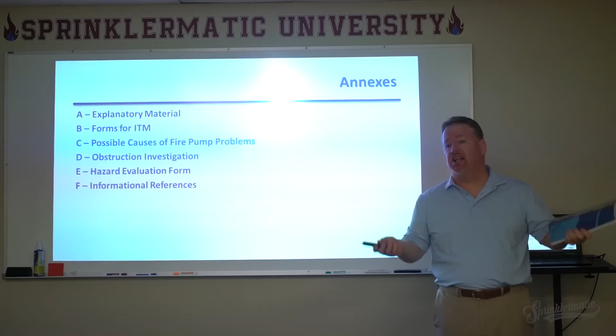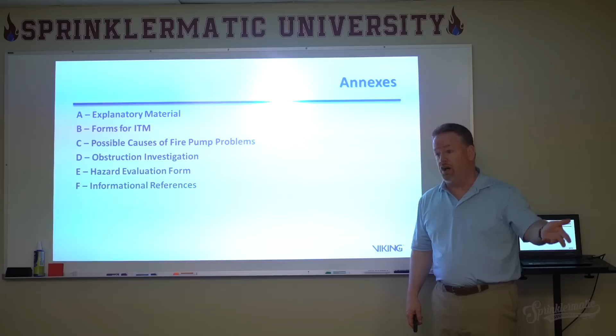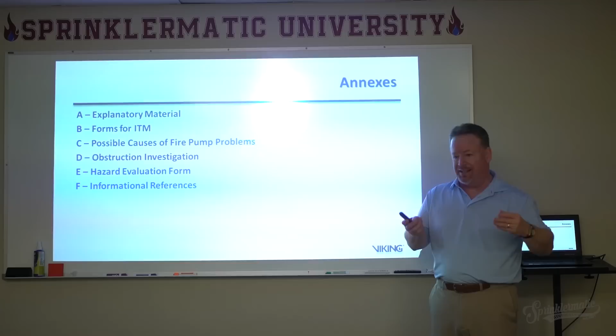Right, it's still NFPA 25, just the 2011 edition, which was the edition I was involved with when I worked at NFPA. This changes every 3 years or so, so you need to know which one is adopted in the state. Just because the 2017 edition is the most recent doesn't mean it's the law in Florida, because it has to go through its own administrative process to be adopted, and that usually lags one or two editions behind the current edition of NFPA 25.